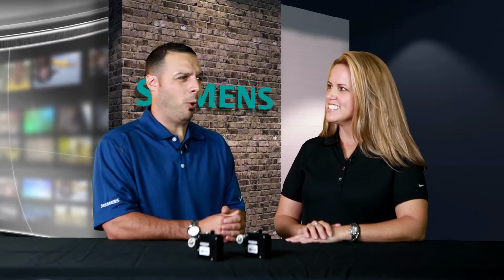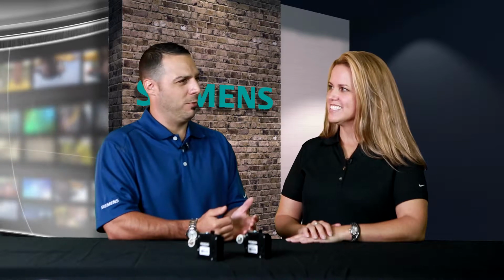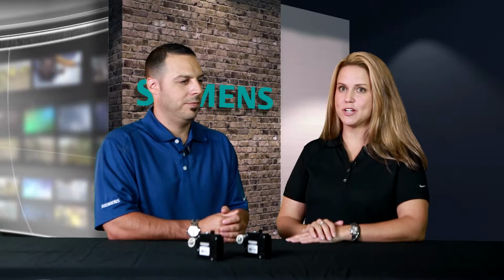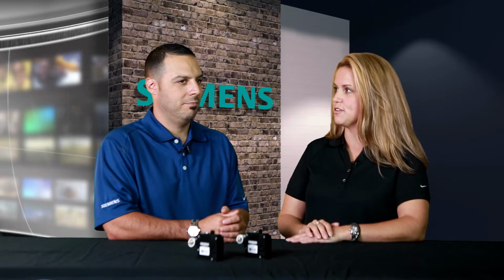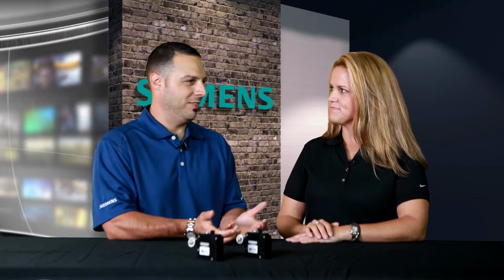So you're saying that a homeowner would have to move a refrigerator in order to get to this receptacle? Exactly. That doesn't sound like it's going to work. No, that wouldn't be so easy on the homeowner. So we have created this dual function device, which now puts the AFCI and GFCI into one circuit breaker. All the contractor has to do is install the circuit breaker, and the GFCI receptacle is no longer required. Thus the dual function. Yes, sir.